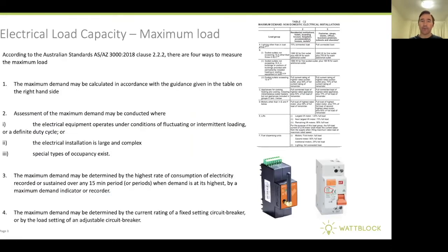According to the Australian Standards 3000, clause 2.2.2, there are four ways to measure the maximum load in the building. It can be calculated in accordance with the guidance given in the table on the right-hand side. The assessment may be conducted where the load operates under fluctuating or intermittent load constraints or a definite duty cycle. The maximum demand may be determined by the highest rate of consumption of electricity recorded or sustained over any 15-minute period by a maximum demand indicator or recorder. And the maximum demand may also be determined by the current rating of a fixed setting circuit breaker or by the load setting of an adjustable circuit breaker.